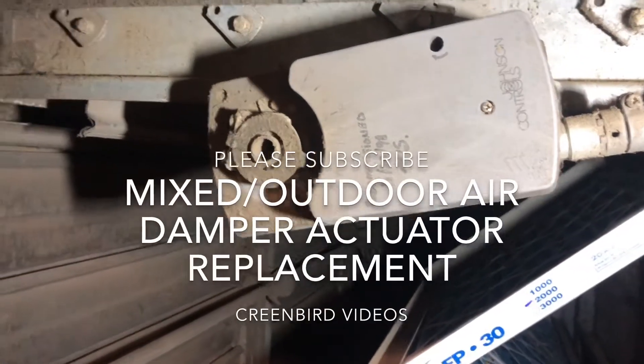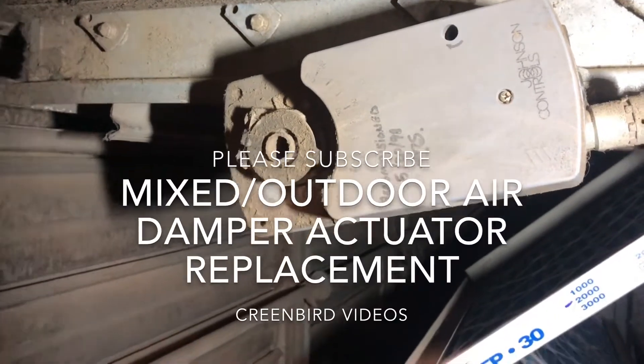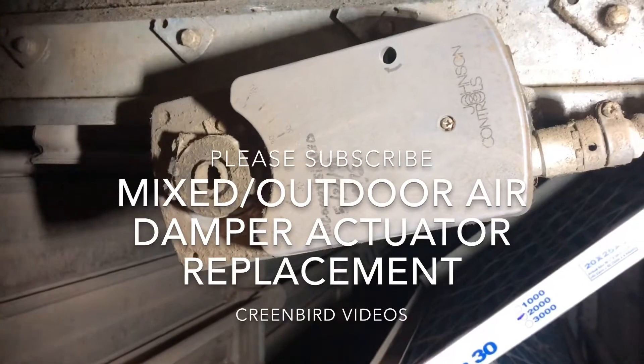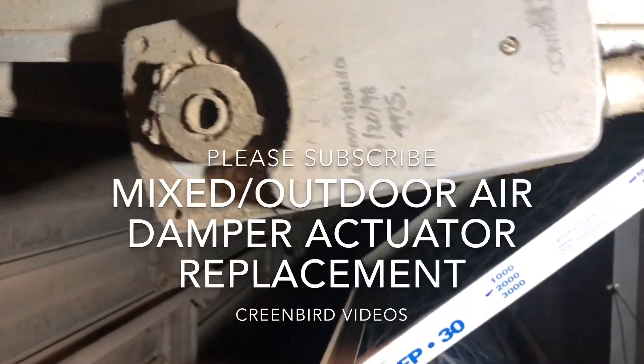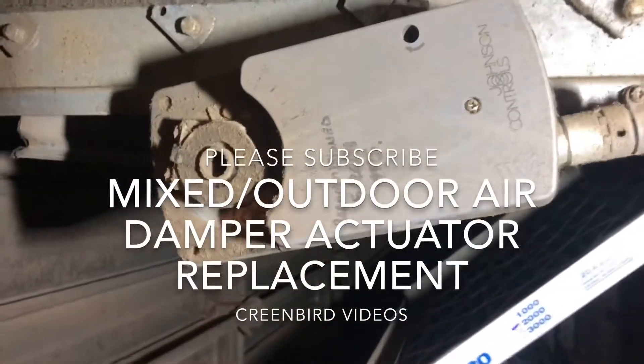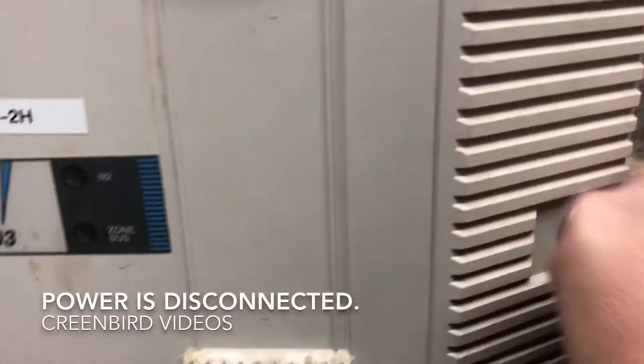Here we have a stuck outdoor air and mixed air actuator. This actuator has been hanging up wide open and not closing as well. Right now it looks like it's stuck at about 30% even though it's all out of whack. So we're going to replace it with the newer model Johnson actuator. We're going to go to our controller box and turn the controls right off.